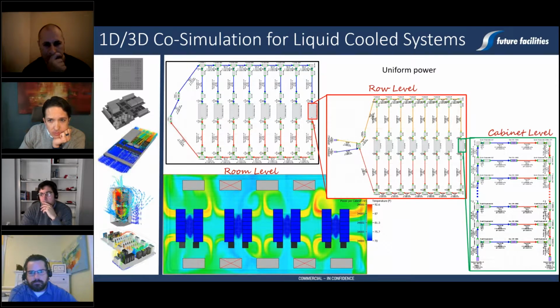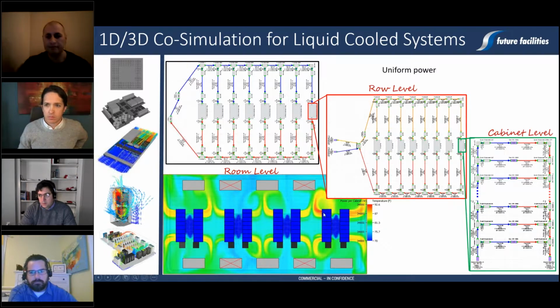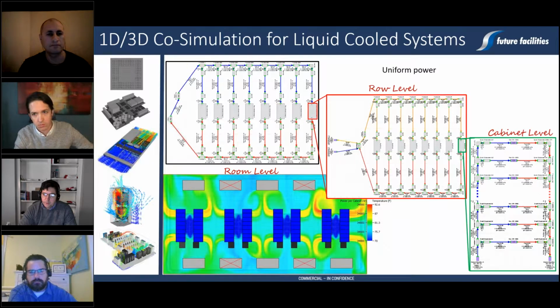This picture is showing something very important to us — that is why we are doing this co-simulation. On the 3D environment, we are seeing some recirculation happening in the room that can only be captured from a 3D analysis. You can see some of the rows that are drawing air from their own exhaust, and this is causing elevated temperature at their inlet. On the liquid side, we are seeing all the information from the pressure drop that is happening in the pipes, in the quick disconnects, in the CDUs, and so on and so forth, and also all the temperature information we are getting.